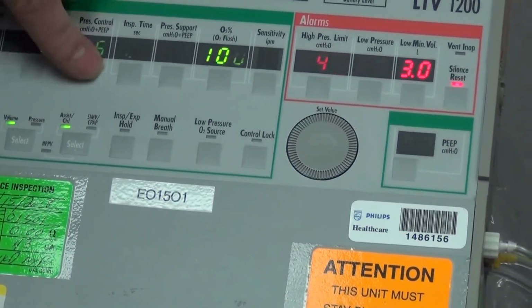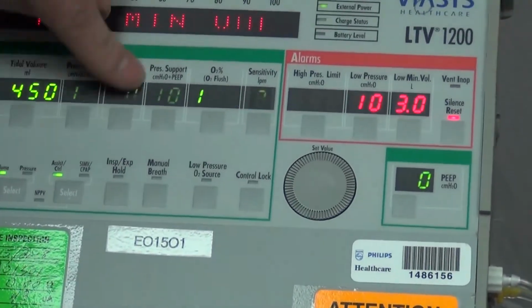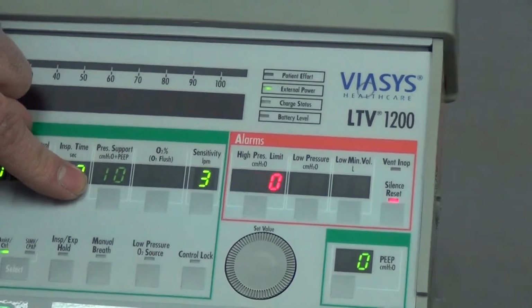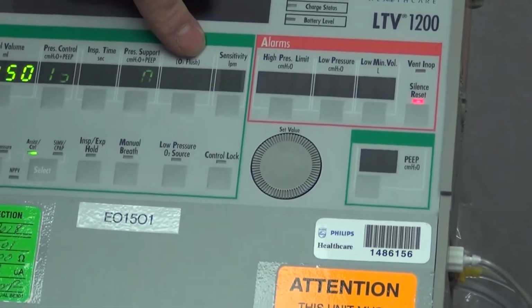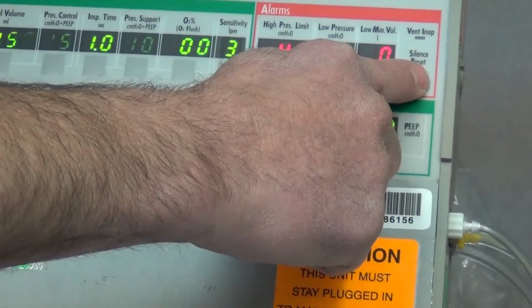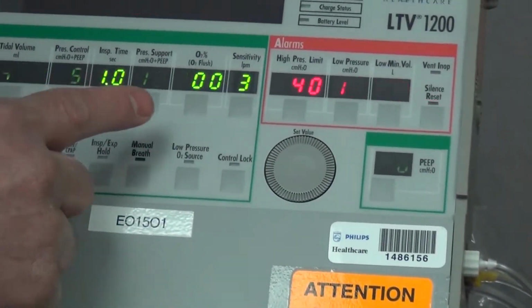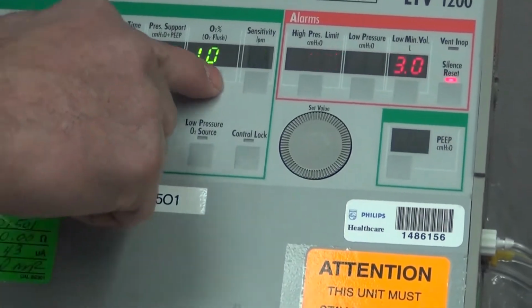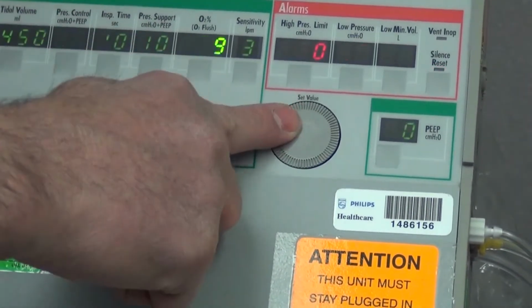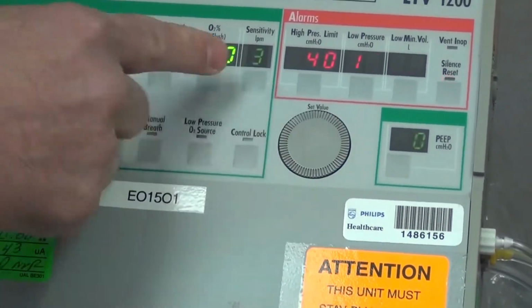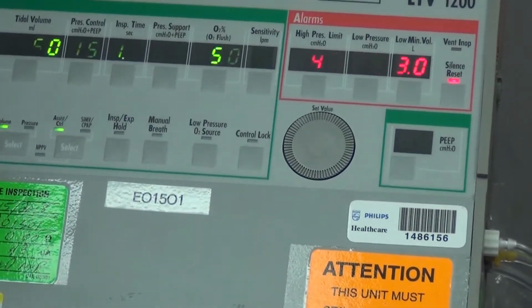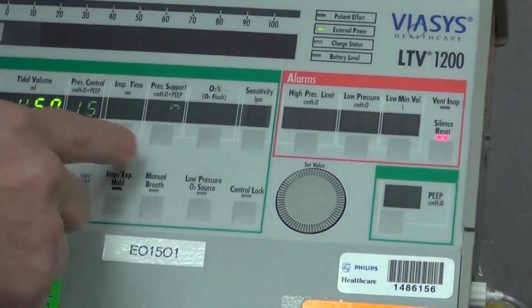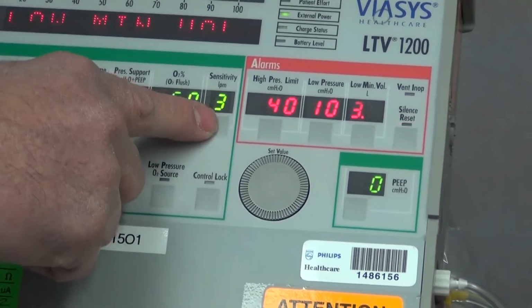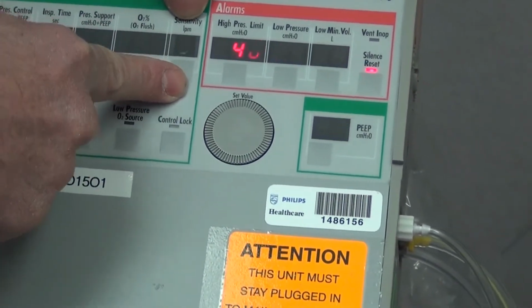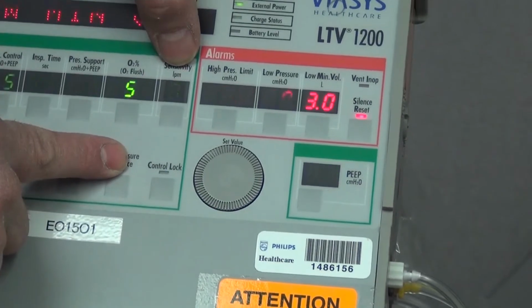This one's grayed out because it's not a setting you can change. Inspiratory time we're going to leave as is. And that is not something that the physician will prescribe. And then your oxygen level. Now I'm going to hit silence again. It just silences for a minute. Oxygen, we usually start with 100. Let's say for now we want to start on 50 for some odd reason. The physician said to start at 50%. Notice they're all lit up. Flow sensitivity is just like on the other machine. We do not touch that one.